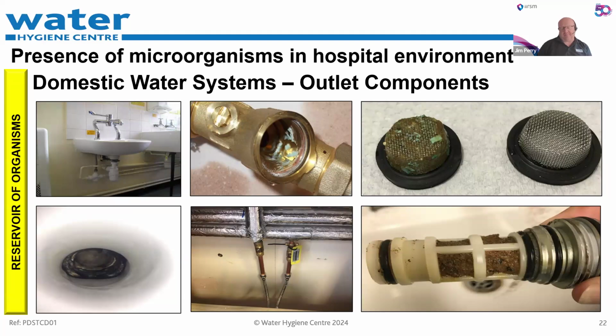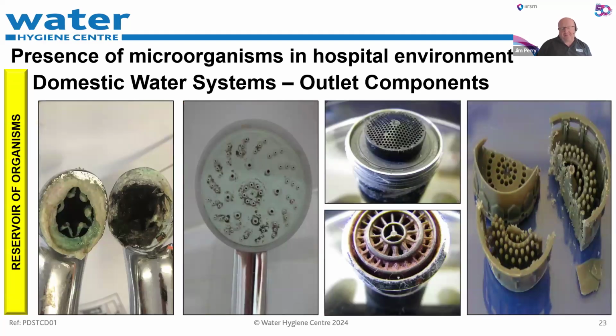We have a few more lovely photos here. Flow straighteners in taps. You can see some nice scale, debris and biofilms built up there. There's a great area for bacteria to breed. A shower head that's not been particularly looked after well. And these plastic inserts that are in our taps and facilities are actually made up of several layers of plastic of differential apertures. So you can see that that's where we can get bacteria building up. It's just going to grow up in those, and then it'll come out eventually once the ecological growth has happened. And that's going to give us a bit of a headache.